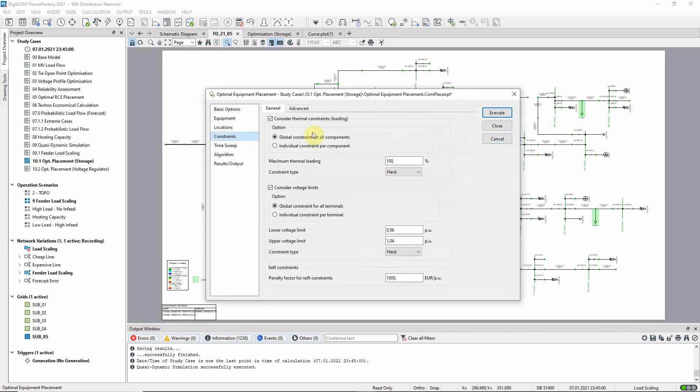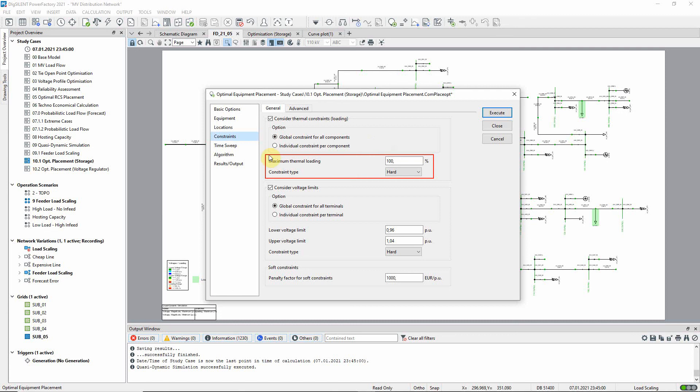On the constraints page of the command dialog we specify that the maximum thermal loading should be 100%. On the time sweep page the command is configured to carry out the calculation for a single day using a time step size of 15 minutes.